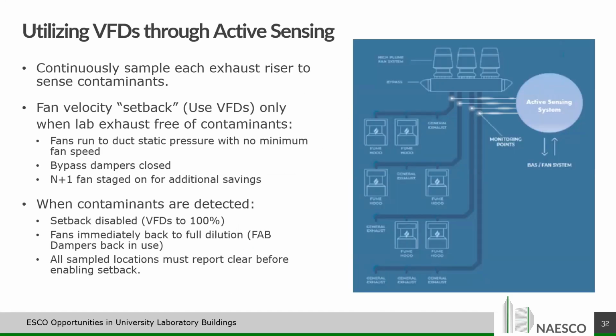Well, recently there's been some solutions in the marketplace that are allowing us to use VFDs on exhaust fans. And it's through active sensing of the exhaust stream from the labs to see if it's volatile or not. So this is how it works. We've got an active sensing system in every riser exhaust plenum in the building. So we're sampling all the exhaust air to see if it's contaminated or if it's clean. And when it's clean, we close that fresh air bleed damper and we enable VFDs on these exhaust fans so that you slow the fans down and you get that motor savings by use of the VFDs.